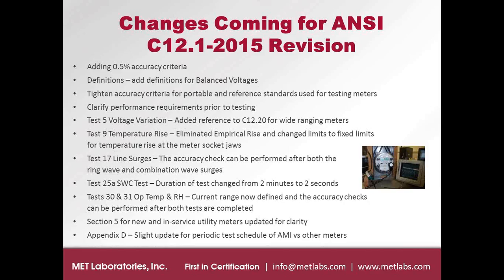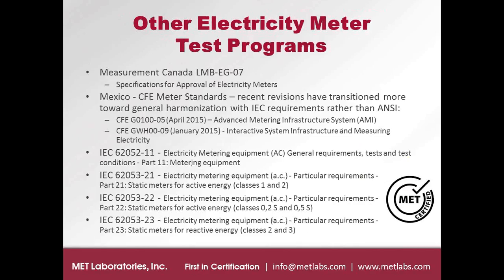And there's been some updated guidance, quite a lot of change really to Section 5 regarding the in-service meters, primarily criteria that's used by the utilities to run annual checks and so forth on meters that are already in service in the field. And some update on the periodic test schedule, again, sort of follows along a bit with Section 5, but the test schedules for AMI equipped meters versus other types of meters. So just some highlighted changes there that is coming to the new revision of ANSI when it is released.